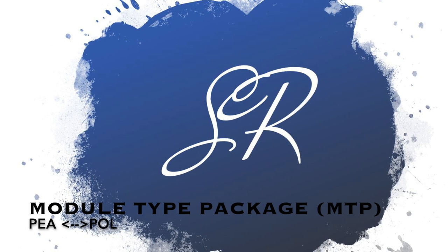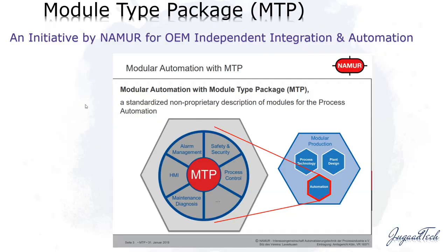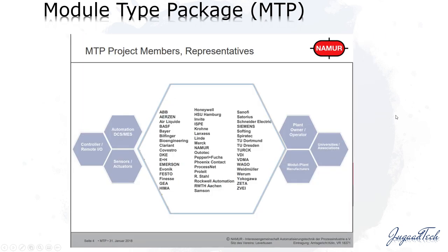Why exactly has NAMUR introduced this MTP and what benefit is it going to bring? MTP, or the Module Type Package, is an initiative to reduce the time spent during the integration between two systems — the UOP and the DCS basically. It is a non-proprietary description of the module for process automation. Automation that is compliant with MTP will make integration easy and OEM-independent.